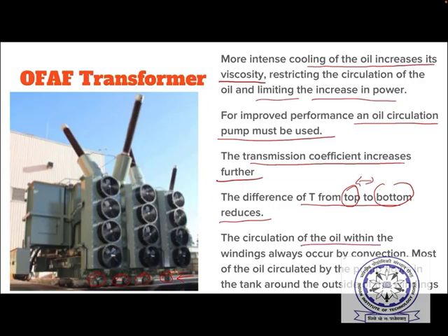Then the circulation of the oil within the windings always occurs by convection. Of course, one thing we have to remember: if you use only pumps, oil will circulate inside the transformer, sure, but the windings are copper strips or coils, supported mechanically by mechanical spacers. So oil circulation through them will be low only. Most of the oil circulated by the pump flows in the tank around the outside of the windings, not through the inside of the windings. So this is the difference between this transformer and the next transformer that we will discuss soon.